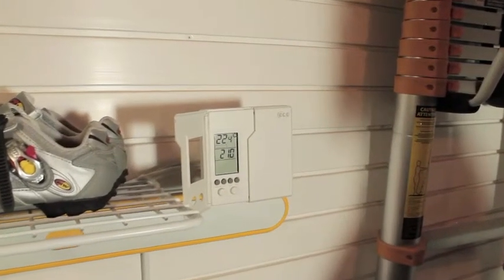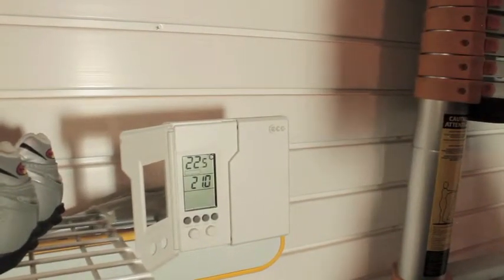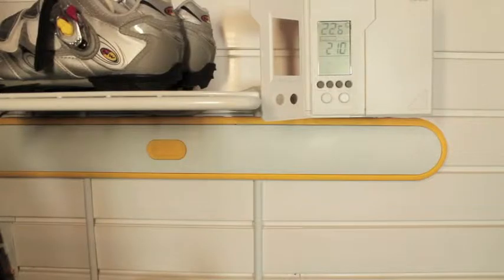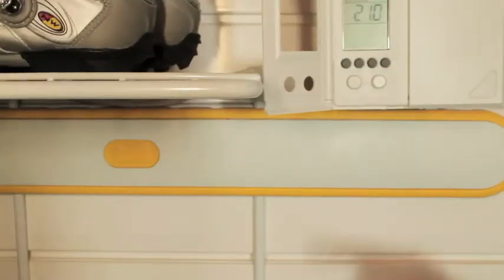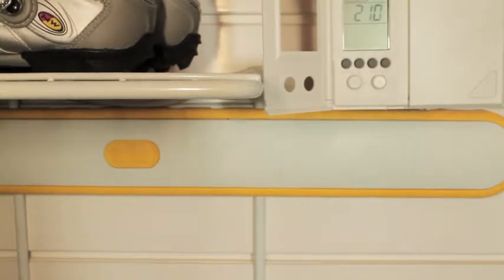Pressing set again advances to the next option which appears as RE. This is the pre-comfort recovery option. When it is set to 1, the thermostat will turn on heating in advance of a program change to get a head start on reaching a warmer temperature. Turning the option to 0 turns off pre-comfort recovery.